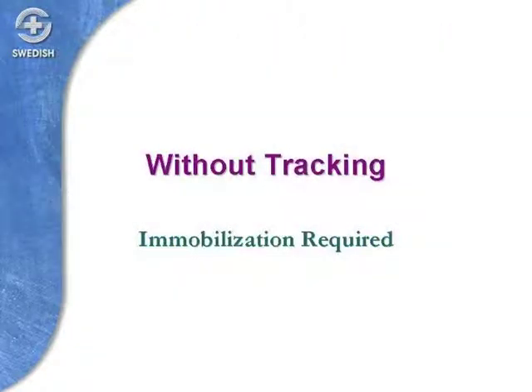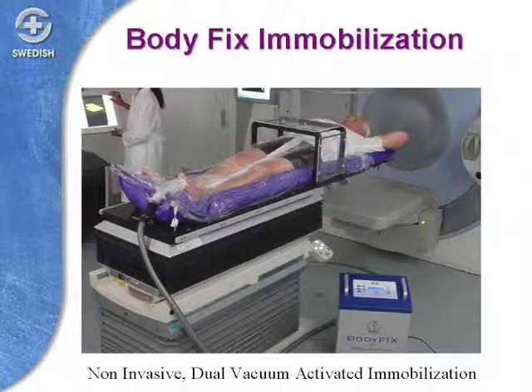You can also treat these patients without tracking and without fiducials, but you need to make sure the patient remains in the same position every time. This device helps position the patient in that exact same position. The purple mattress shown is a mold built for each individual patient — as they lay in it, it hardens to the shape of their body so they're in the same orientation each visit.